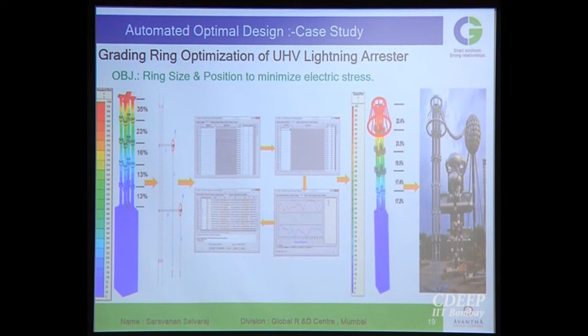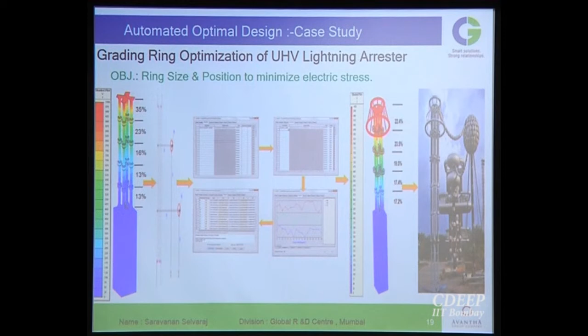this shows the voltage distribution of the lightning arrestor. The top point is connected to the line, and the bottom point is at ground. Because of the stray capacitances, there is a non-uniform voltage distribution along the height. Because of that, the chances of failure are more. So the need is to equalize the voltage distribution along the height of the lightning arrestor. For that, grading rings are used, the ring shown at the top. The objective function is to arrive at the minimum size of the grading ring and the position of the grading ring.